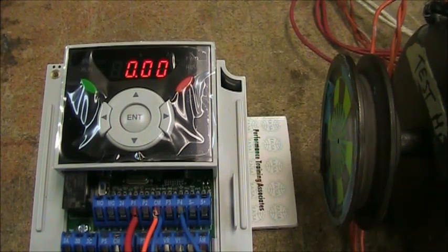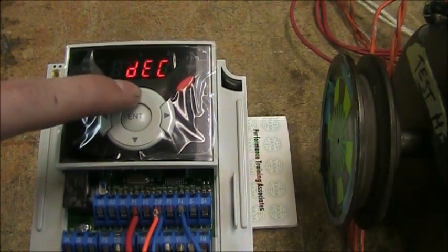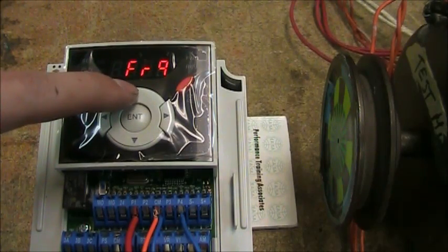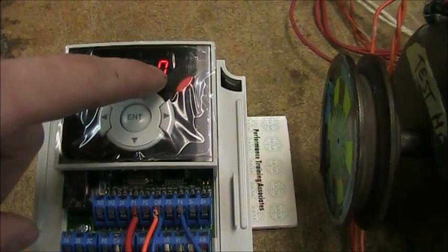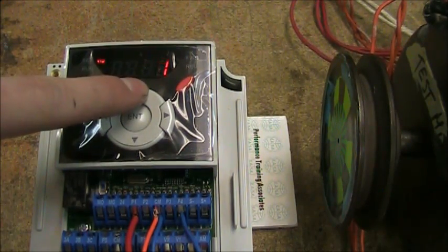Based on the manual, the frequency setting method is parameter FRQ, which is in the main drive group. So as I said before, the main drive group is from the main screen, so I'm going to hit the up arrow until I see FRQ on the display. To get to that parameter, I'm going to hit enter. The value of that right now is 0, which equals keypad as the reference. And since I'm using terminal V1, I'm going to put that parameter to 2.